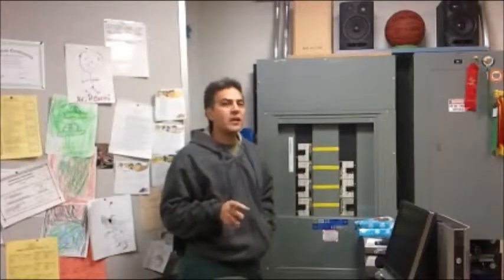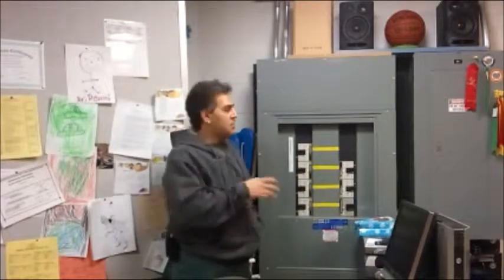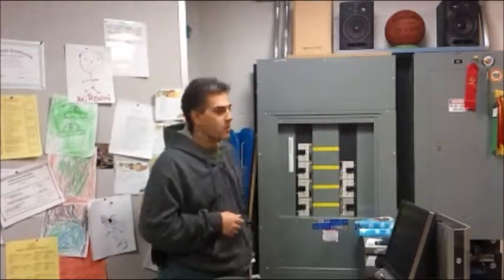And over here to my right is where we're going to put a transformer. The kiln runs on 208 3-phase. This panel is not 208, it's 480 volts. So in order to power up the kiln, we have to drop the voltage a little bit. We do that by means of a transformer. And I calculated out, we're going to need about a 15 kVA transformer, which is going to pump out close to 50 amps. Offhand, I don't know, I'd have to look at the book. But I did research it, and that's what we're going to need, a 15 kVA transformer.